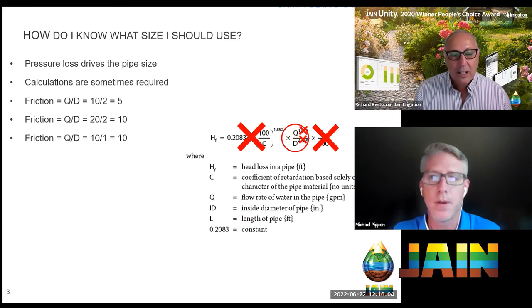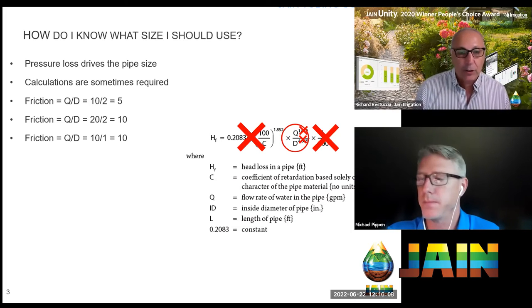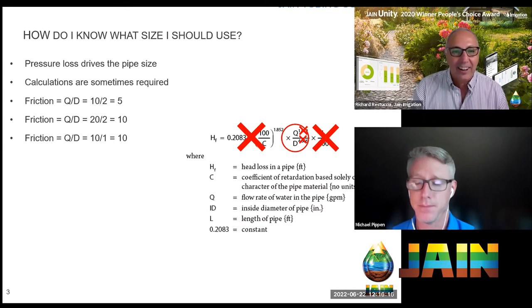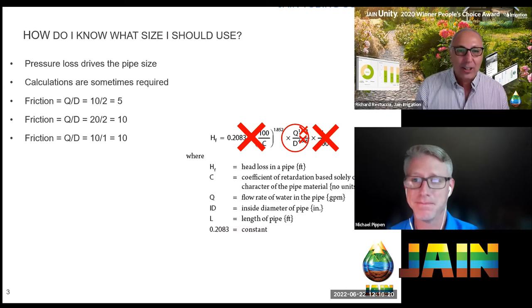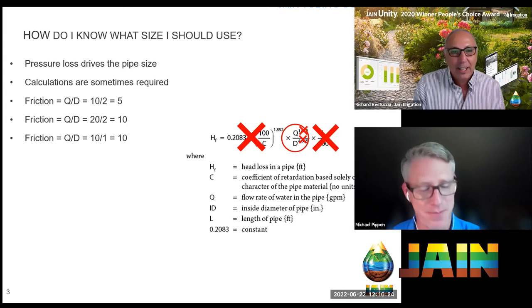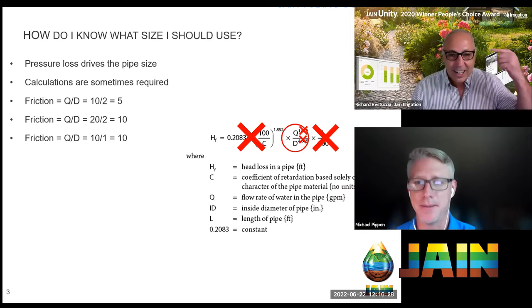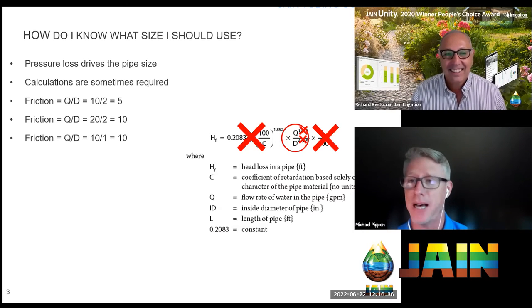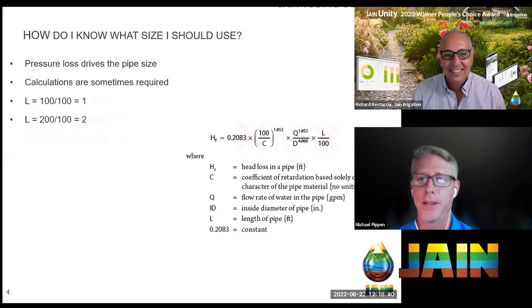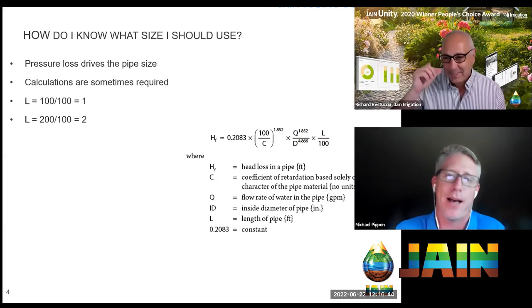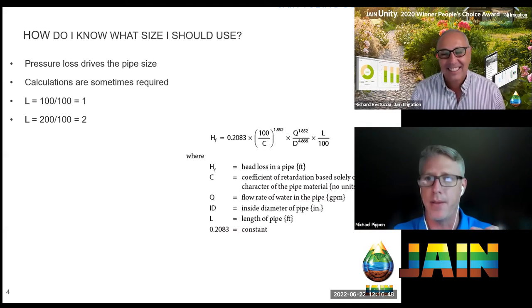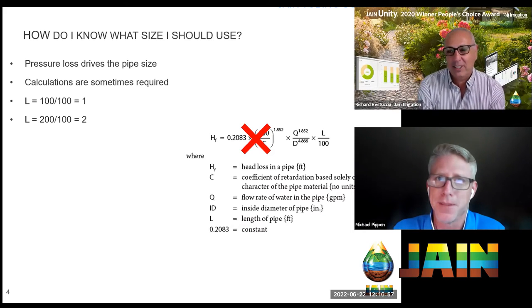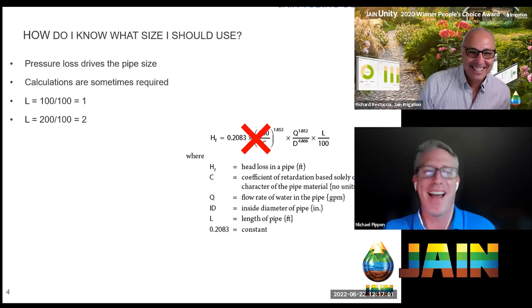Over here on the left-hand side, I've simplified it. This friction loss is your flow rate over your diameter. I'm going to make these numbers up. These numbers don't mean anything. But if your flow rate was 10 and your diameter was two, imaginary numbers, then your friction loss would be a five. But what happens if I increase my flow rate? I go from 10 to 20 on this Q, but I keep my pipe size the same. Flow rate has gone up. Pipe stays the same. What happens? Our pressure loss goes up. Here's the one that is the most common misconception in pipeline design. We've kept our flow rate the same, it's 10 here and 10 here. But what I did was I decreased my pipe size. I went from two to one. What happens? Our friction loss goes up. I've heard it from designers, contractors, installers. Man, I need that little pressure at the end. So I neck that pipe down to boost that pressure up right there at the end. That is absolutely incorrect. Decreasing the pipe size, if your flow rate stays the same, will decrease the pressure in that line. It will increase the friction loss. It will not boost that pressure on up. It will bring that pressure on down.